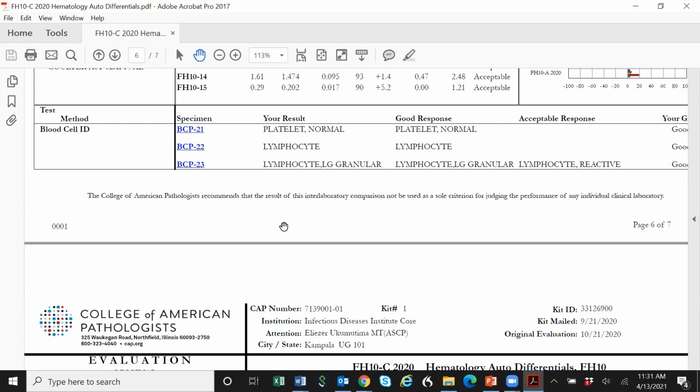And then for labs that can't afford to be enrolled in an EQA program, does doing comparison of results with other labs pass as proficiency? Yes. Comparison, absolutely, yes, and that's a great question. I would encourage you to just document it. So lab A selects samples that are blinded to lab B, and you send it to lab B, and you cross-check with them, and you come up with ranges that are reasonable for matching. Yes, that counts, absolutely. All right, great. And I would encourage it.